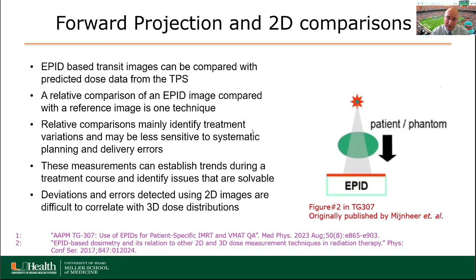So, three-dimensional dose, going through that same process. Again, we're collecting the data as it exits the patient with the EPID, and then we're typically using back projection methods to reconstruct that dose back into the patient frame of reference. So it's either the planning CT or the cone beam. And so now you have a 3D dose distribution inside the patient, and you can compare that 3D dose distribution back to the original TPS distribution. So you can look for changes, and you start to see where inside the body these changes are occurring.